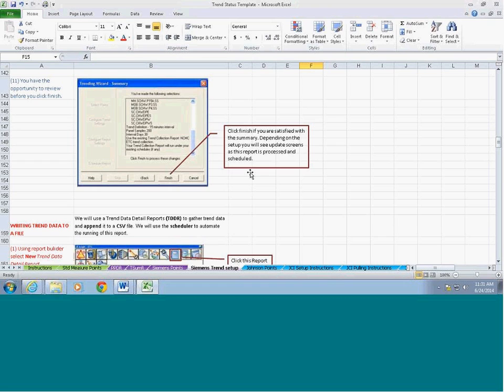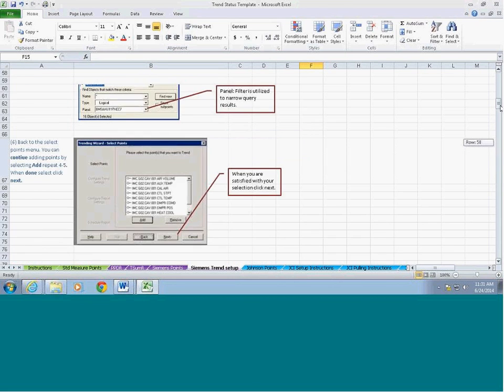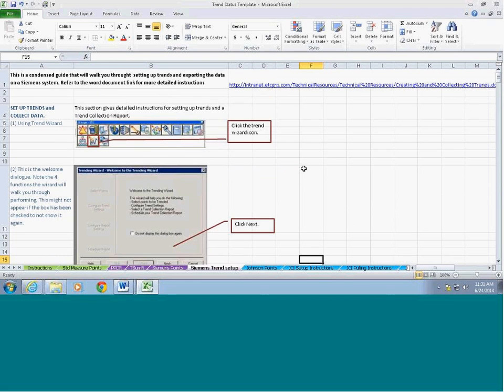What was really recommended is 200 samples, because typically you're doing 15-minute interval trends, and that's just over 2 days. The nice thing about having just over 2 days is that if you collect daily, and you miss the opportunity to collect, you come back the day after and still have enough for that whole day before.